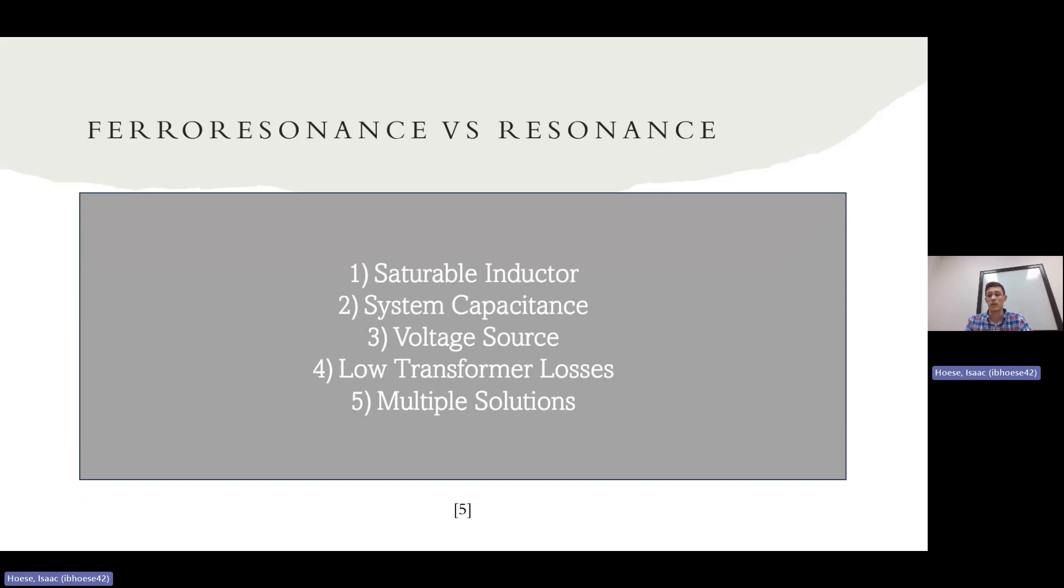Kruger, which is an author that I'll be citing multiple times in this presentation, states that there are five main reasons or requirements for ferroresonance to occur. First is the saturable inductor. That's the iron core of the transformer. Number two is system capacitance. In our case, it'll be underground cable. Number three is the voltage source. Obviously, all power systems have a voltage source, whether it's the transformer or the generator, whichever one you want to take as your voltage source.